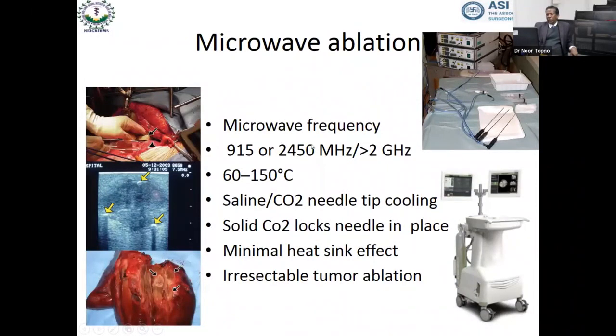Now again, microwave ablation, here the energy used is even higher. The conventional machines used to use somewhere from 900 to 2500 megahertz. But the newer machine, the lower one which you see, uses energy which is much more than 2 gigahertz. The temperature which is attained is around 60 to 150 degrees centigrade. And the important thing is this effect happens very, very fast. And the tip has to be cool. So either saline or carbon dioxide is circulated through it to bring about a cooling effect.